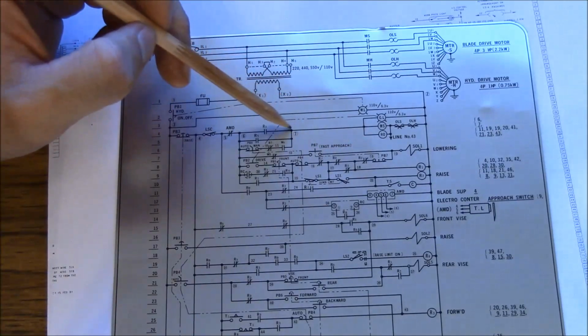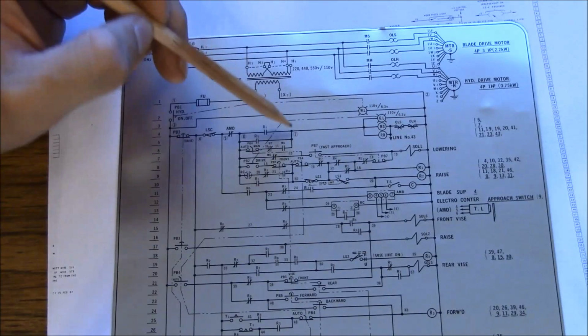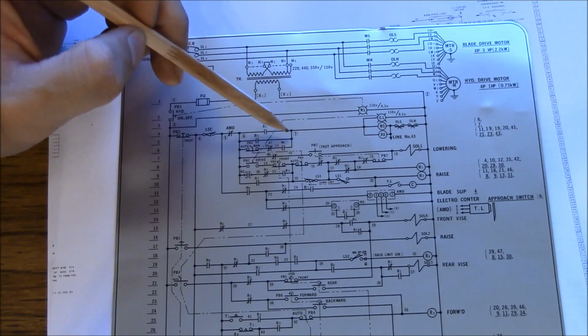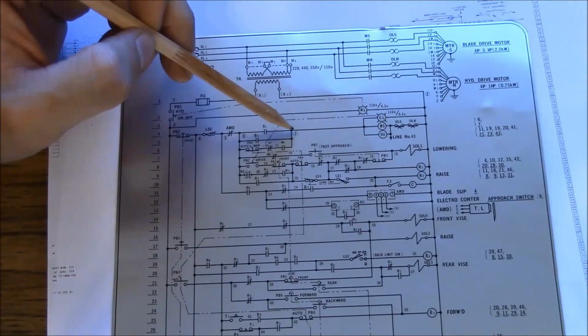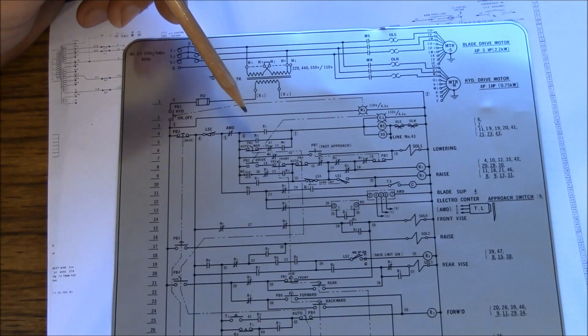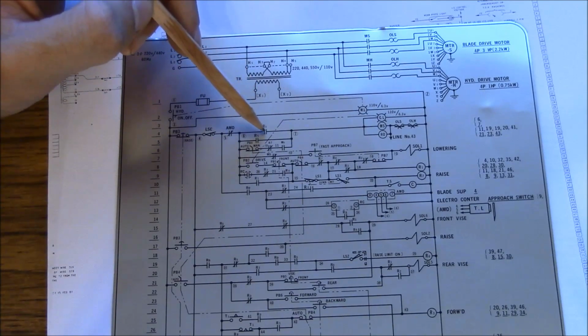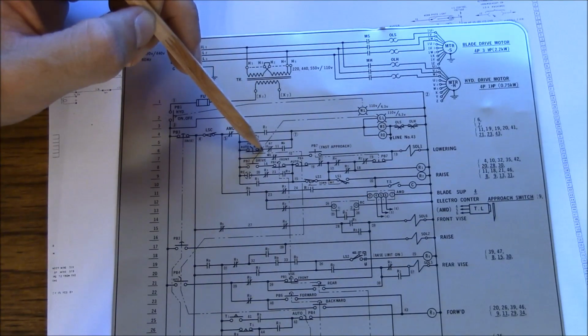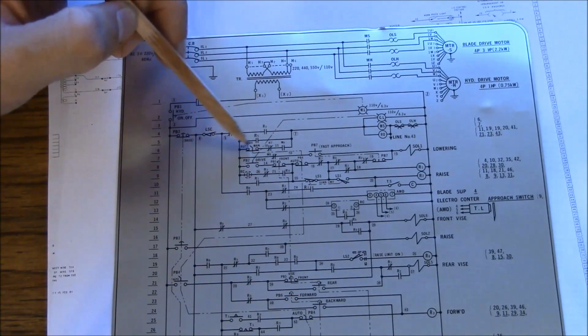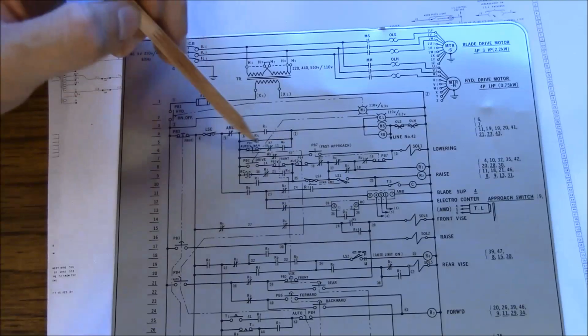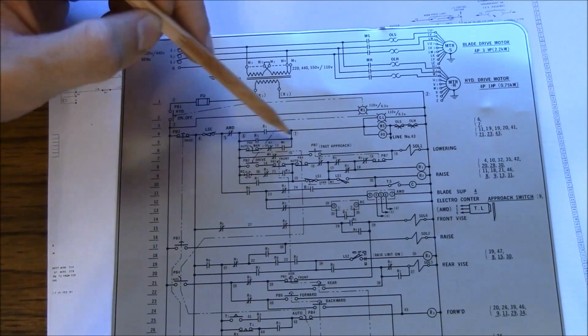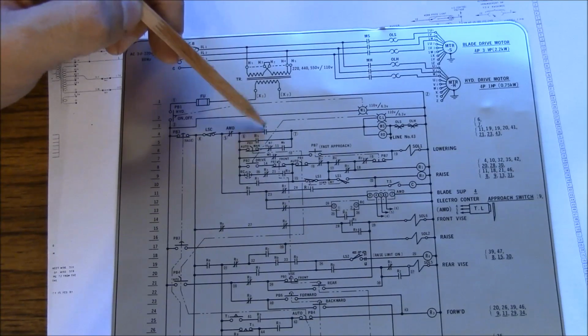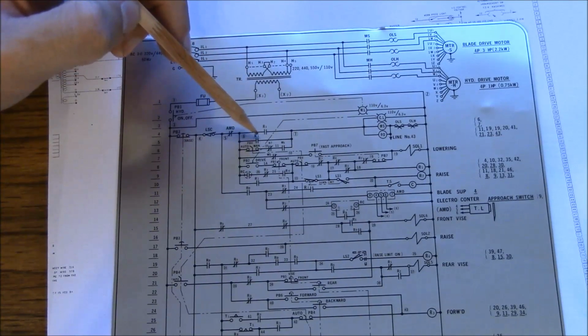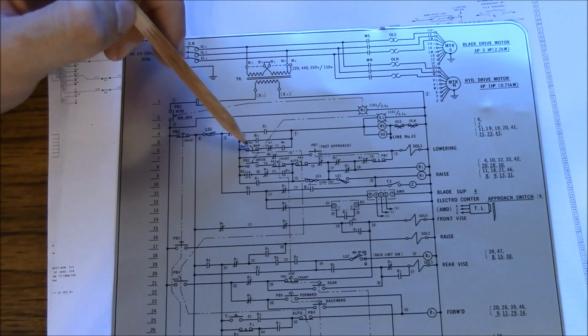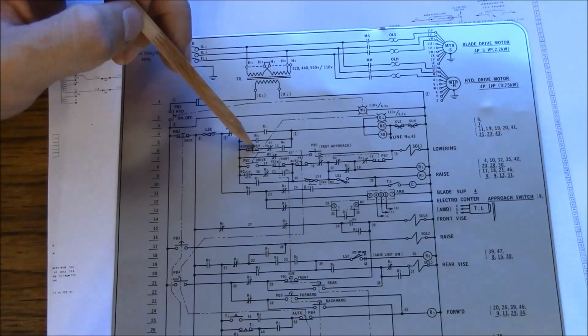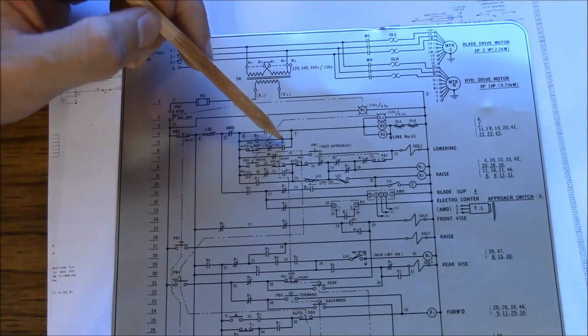So looking from this side, see that we get power to MS from this terminal here called 7. So 7 probably represents the wire number. And now it's going to get confusing because we have 1, 2, 3 different paths for power to come through. These are parallel connections or logical OR connections. So if R1 is pulled in, it gets power to 7. If R5 is pulled in, it gets power to 7.